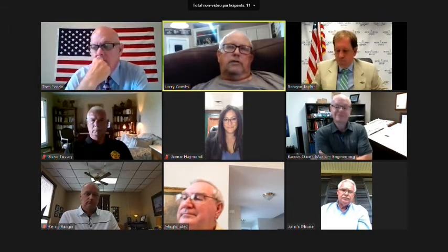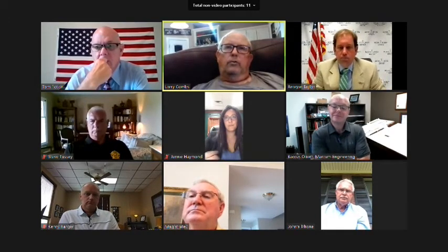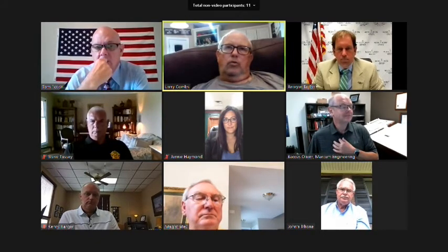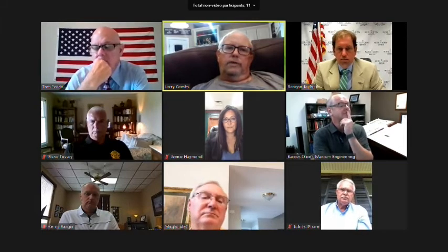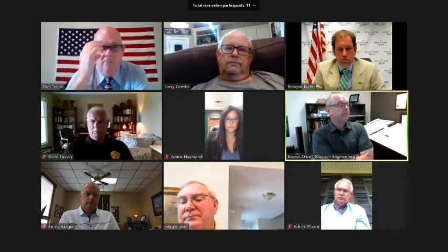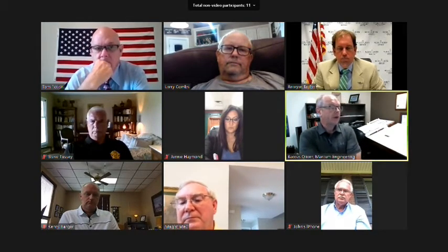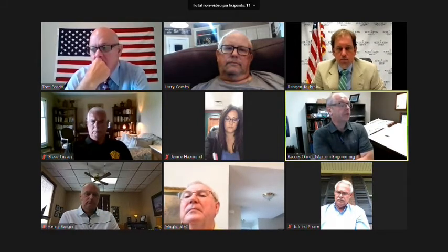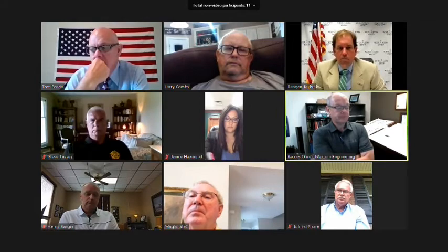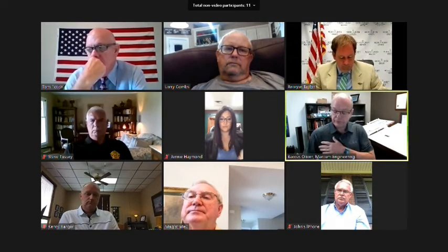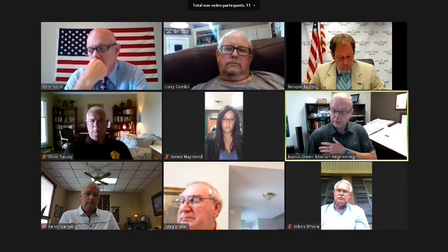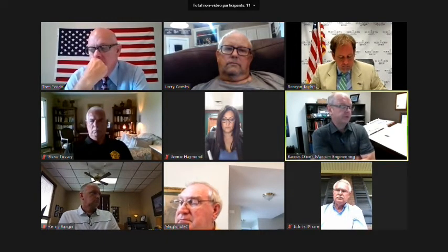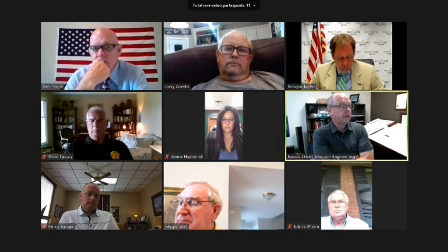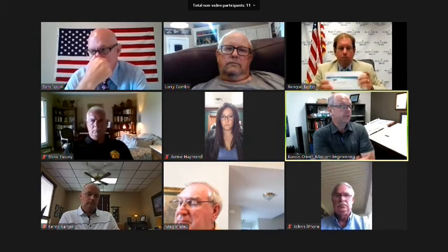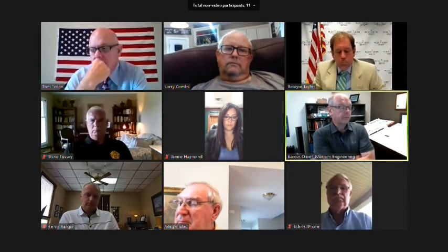Right there. Is there any one or two things that we could do, say, as of now, that would buy us a little more time instead of having to come up with all that money at one time? Yeah, if I was to take that necessary column and say critical, then the necessary critical items are the fluid cooler, the DOAS unit, and the controls to control those things. So that would remove 122,000 from the 438, which gives you a new total. The critical items, I think, are 316,000. I still think the boiler is necessary, but it could be put off because of financial means. And the optional items could just be put off.